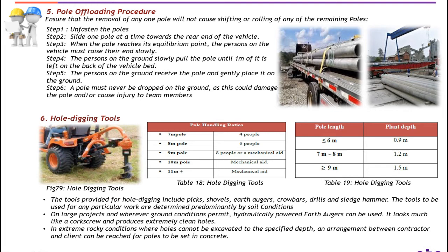The tools provided for hole digging include picks, shovels, earth augers, crowbars, drills and sledgehammers. The tools to be used for any particular work are determined predominantly by soil condition. On large projects where ground conditions permit, hydraulically powered earth augers can be used — they look much like a corkscrew and produce extremely clean holes. In extreme rocky conditions where holes cannot be excavated to the specified depth, an arrangement between contractor and client can be reached for poles to be set in concrete.